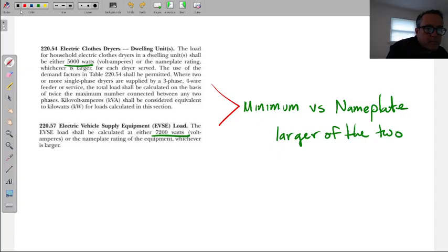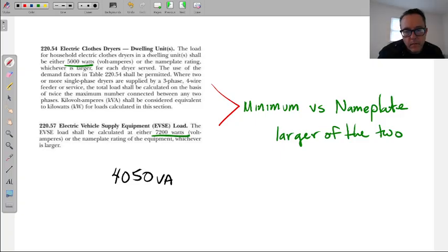If we were, for example, let's just do a quick side here. If we came up with a general lighting load, right, after we did the 35% and calculated, and we came up with a number that we had yesterday, that's why it's in my brain right now, 4,050 VA, then I would divide that, if I'm trying to find breakers, by 120. Believe this is what we did in week 1 or 2 with that 210 article. All right, we divide now 4,050 by 120.